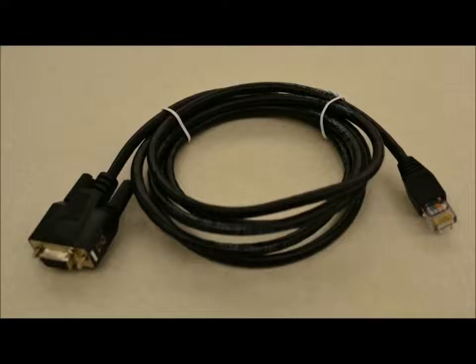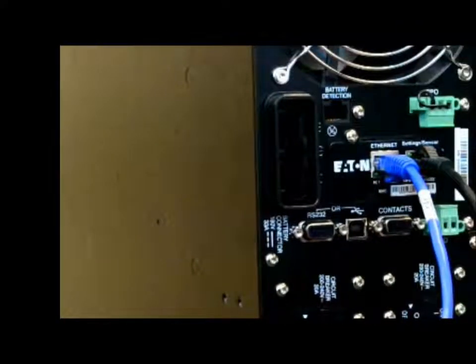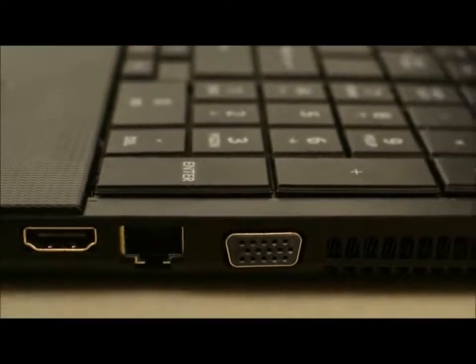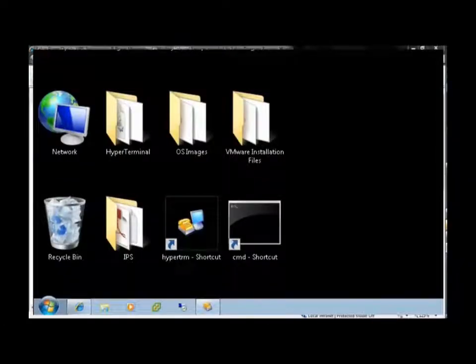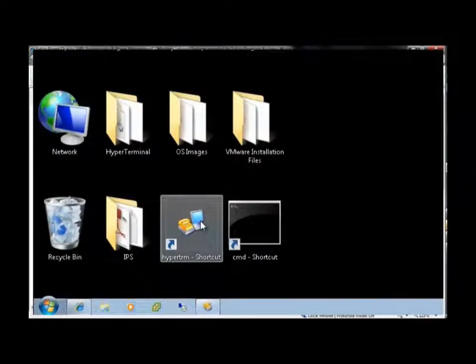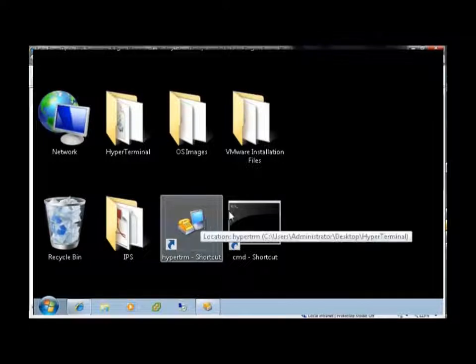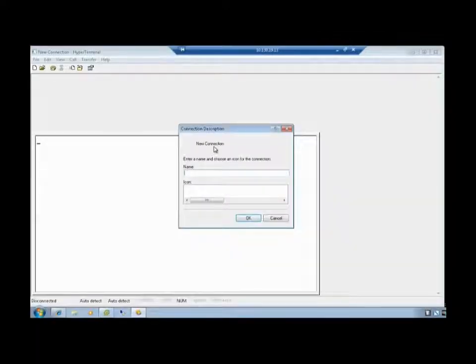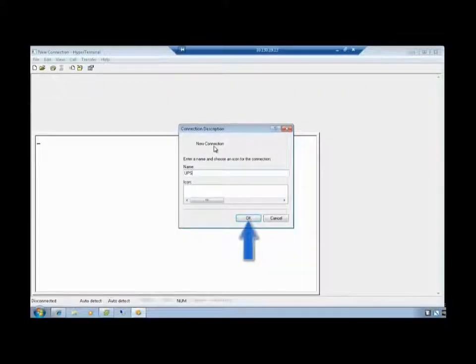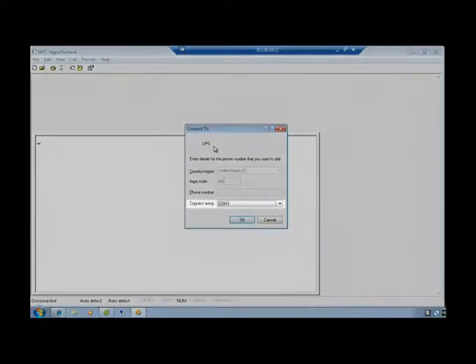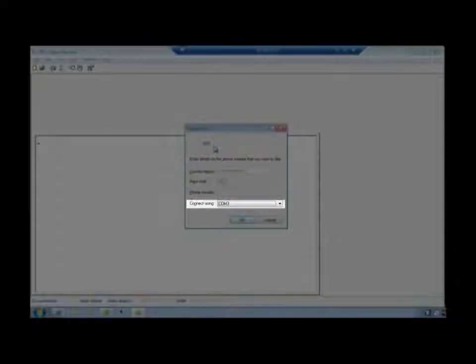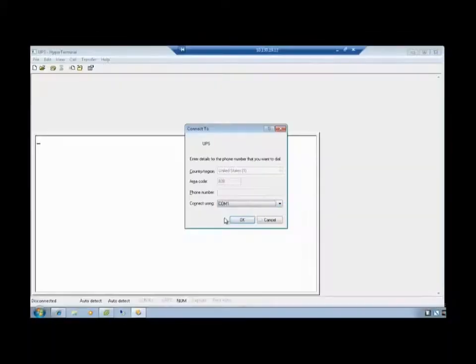To begin, connect the loose end of the RS-232 cable, which is connected to the setting/sensor port of the Network Management Card, into the COM port of a PC. Once the physical connection is made, launch a hyperterminal type emulator to configure the serial connection. Once launched, the connection description text box will appear. Enter the name desired for the UPS system and press OK. Using the Connect to text box, choose your designated COM port for your connection and select OK.